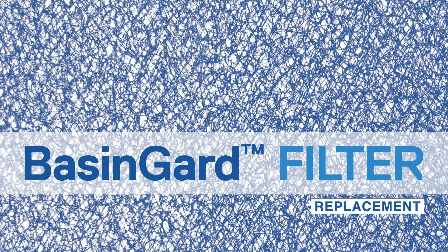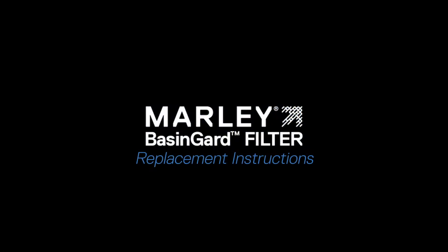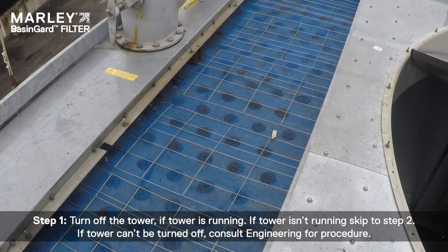The Marley BasinGard filter saves time and money by simplifying the cleaning of the cooling tower's hot water basin and protecting cooling tower components. Here we'll take you through the steps to easily replace your BasinGard filter. Step 1: Turn off the tower if the tower is running. If the tower isn't running, skip to step 2. If the tower can't be turned off, consult engineering for procedure.